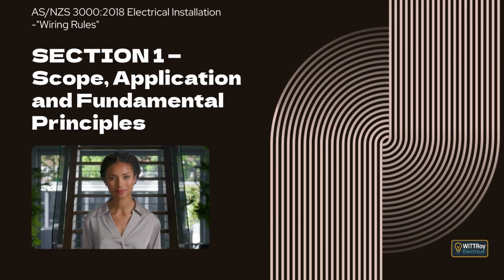If extra insulation is added on site, it must be fitted properly. There should not be any metal screws or bolts that break through that insulation. Any covers or lids that can be opened without tools must still keep live parts safely behind an insulating barrier that meets the correct IP rating.